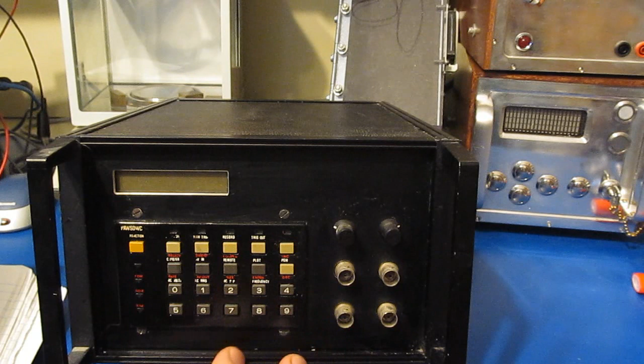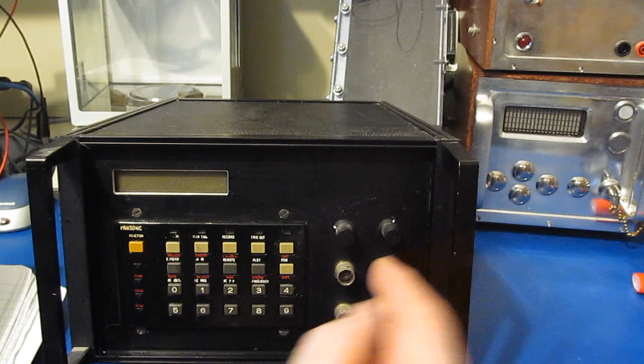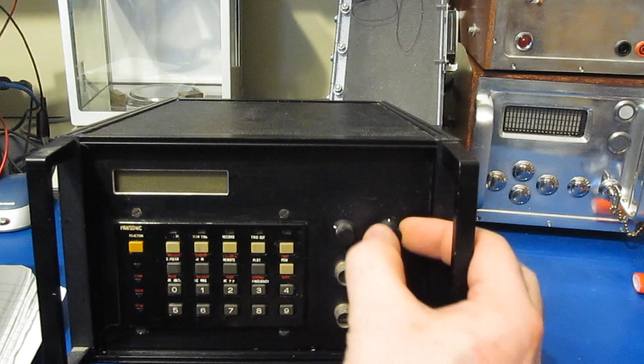So let's say you had a 1 megahertz analog scope and you were going to try to increase the bandwidth. If you didn't want to lose any information, one way that you could do that is you could use a digitizer like this, capture the data at say 10 megahertz, and then play it back. It's something that the scope could handle. So again, we'd have some kind of an output trigger that would drive the scope's input trigger, and that would be delayed, and that would allow us to basically index through that captured waveform.